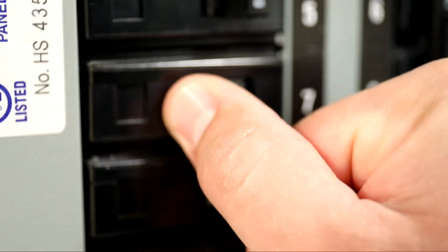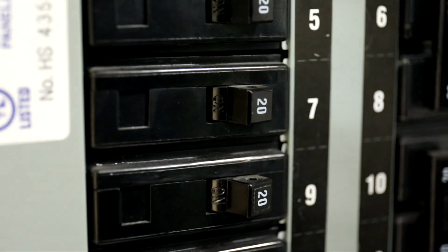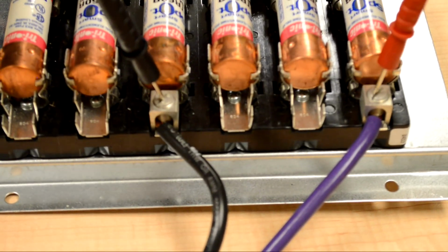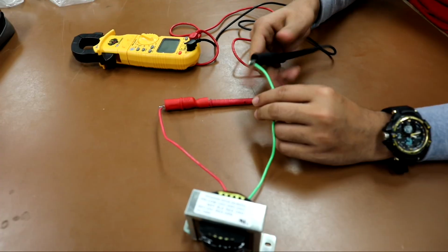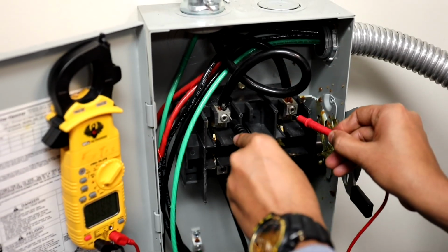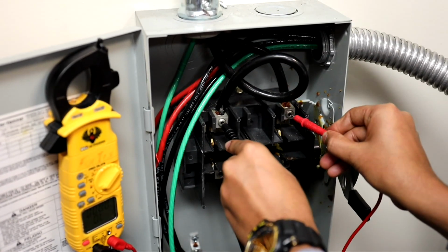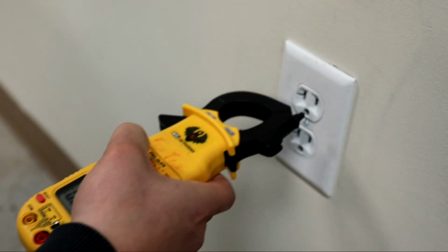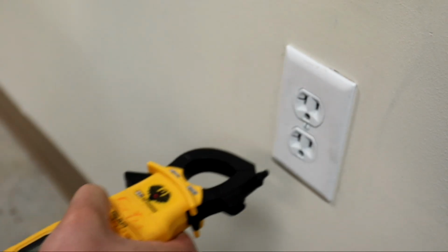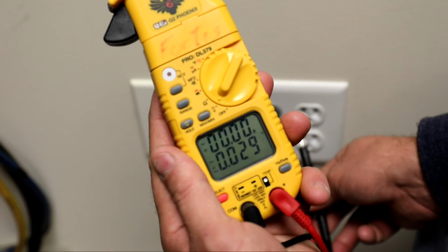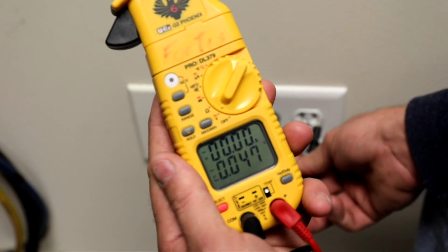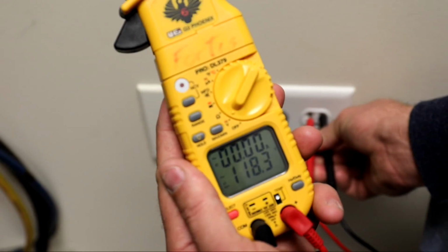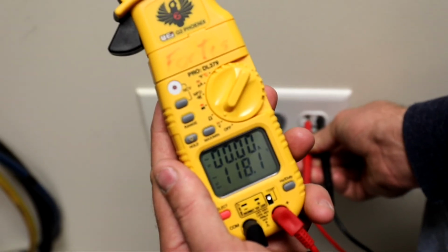The power source must be turned on in order to check voltage, and the meter leads must be connected to opposite poles or on opposite sides of a load or the opposite sides of a switch in the off position. Some meters also have a non-contact voltage tester which allows a quick evaluation of whether the power is on. A voltage test is to determine whether the supply voltage is in an allowable range and does not measure power or watts.